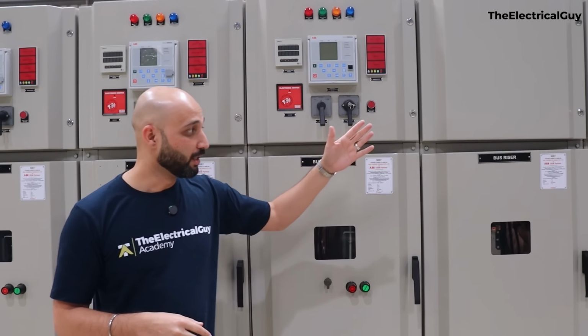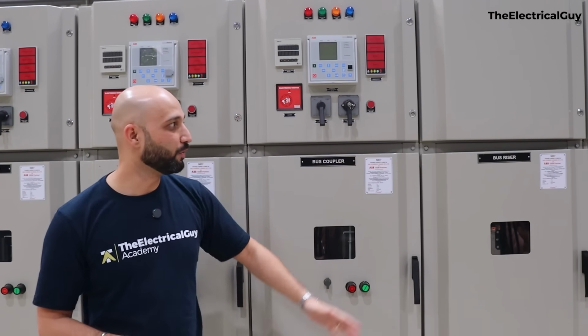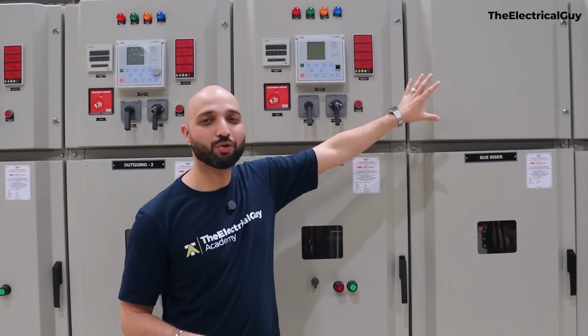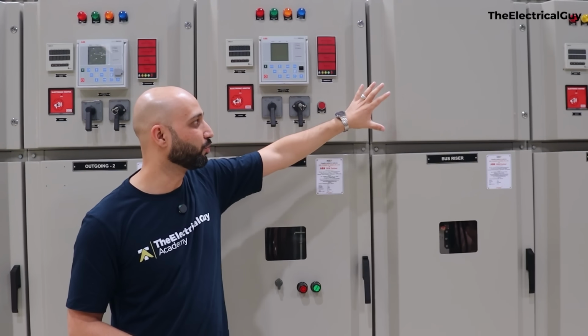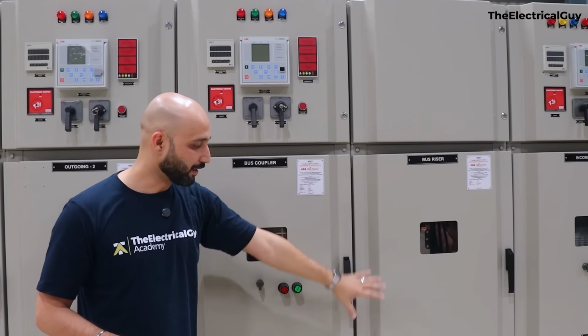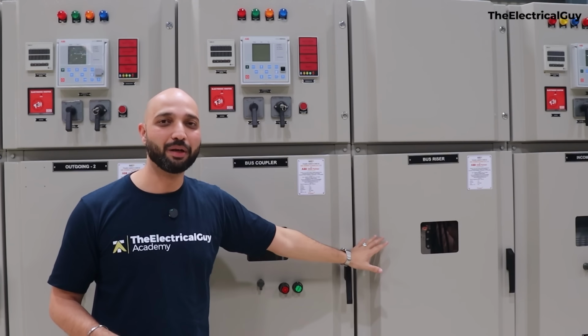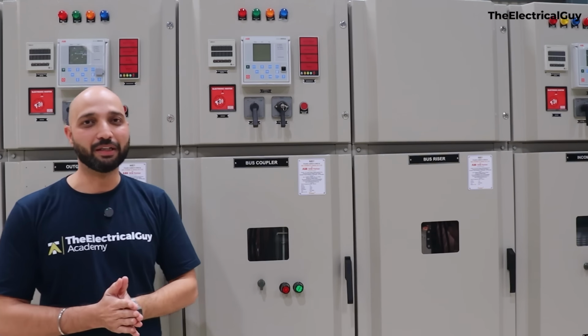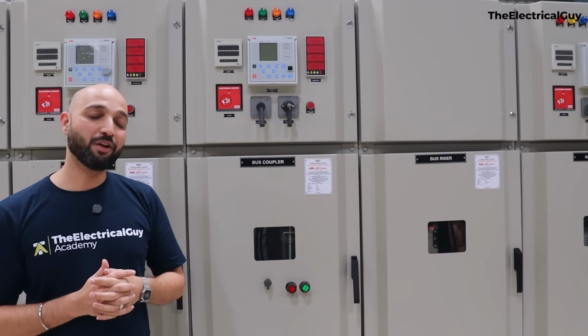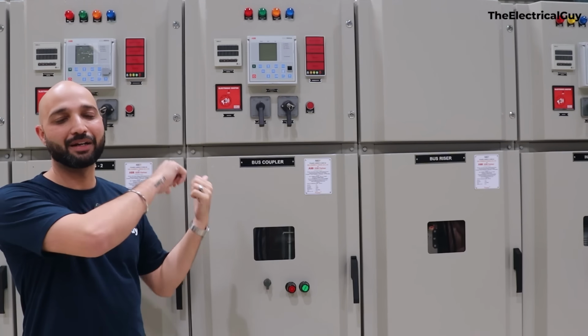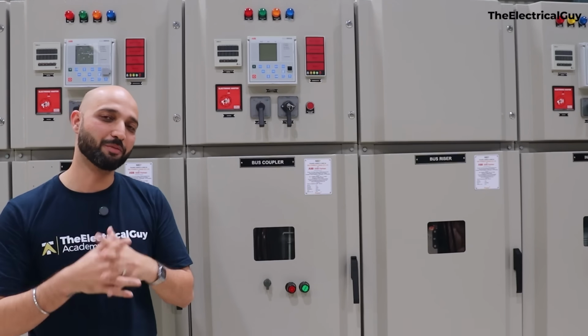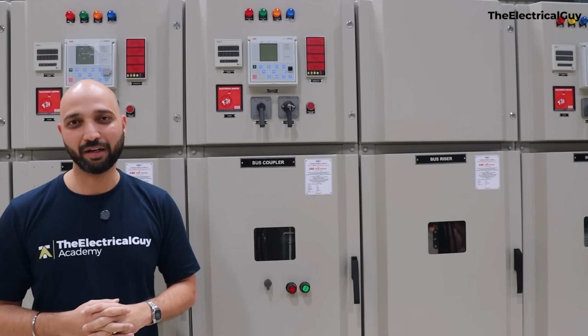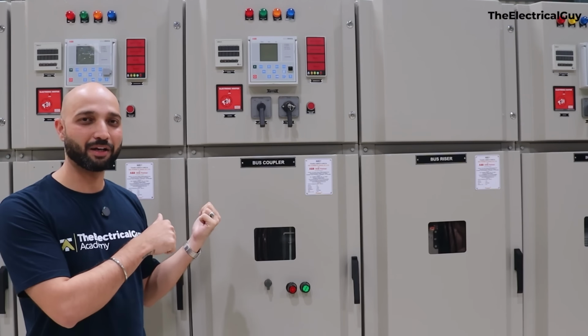Now the question is, why do we need the bus riser? And you will see it's absolutely blank. There is no low voltage side to it. There are no meters. There is no relay to it. And even if I open this and show you, there is no breaker to it as well. Why do we need this? So in order to understand why we need the bus riser panel, we have to get to the back of the panel where I can show you the bus bar arrangement, and you will get a clear idea of that. So now let's get back to the panel.